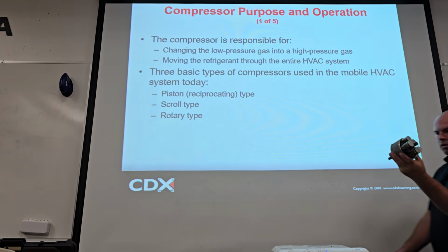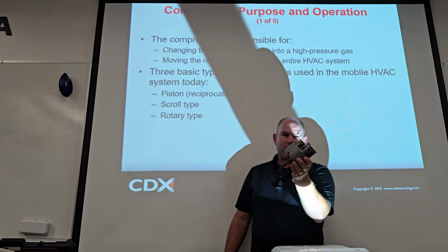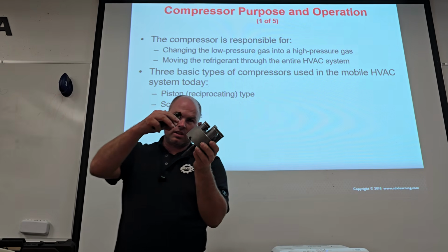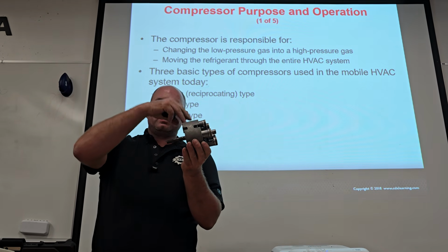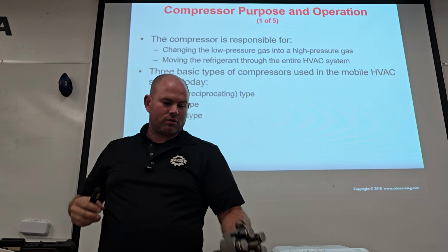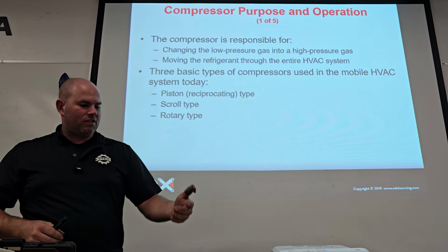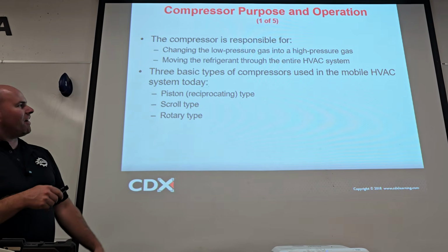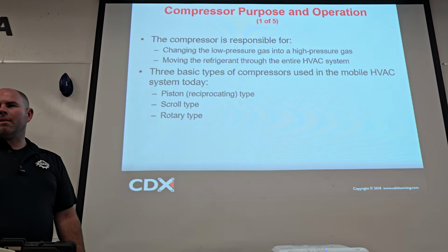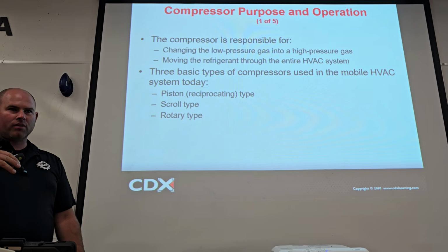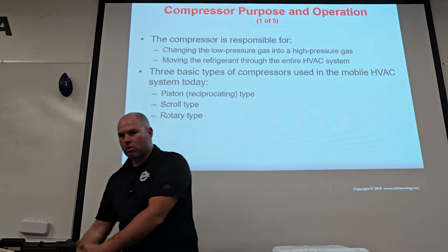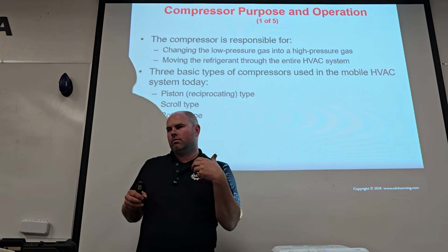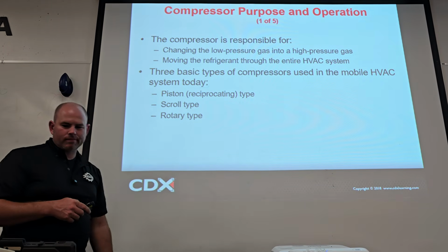So these are actual pistons in a reciprocating type compressor. These actually pump. Makes sense? I can't really make it work that well, but these will literally pump refrigerant. That's what the compressor does. If the compressor's worn out, it would be evident by your high not being high enough and your low not being low enough, right? The compressor should build a high and pull a low. Cool? That's its job. Circulation.